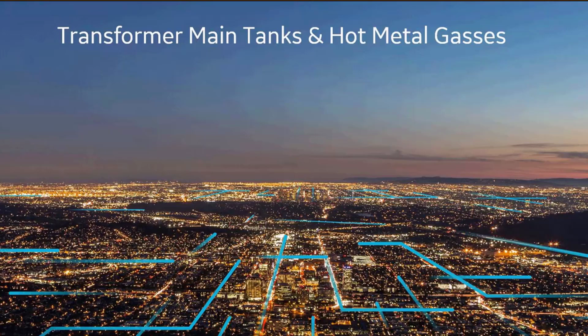So early on, before DGA, we used what's called—and many of us still use it today—a transformer combustible gas analyzer. I didn't put any pictures up of these combustible gas analyzers. They were portable, came in like a suitcase, about yay by yay, wasn't very thick. Had a couple of jars of a mixture of glycerin and, I think, distilled water. You would use them particularly on nitrogen blankets, where you'd open the valve a little bit and run some of that into the blanket through that device, then turn it off, mix that up, and bring that gas back. Once it equalized, you'd bring that gas back across some filaments and read a combustible gas level.